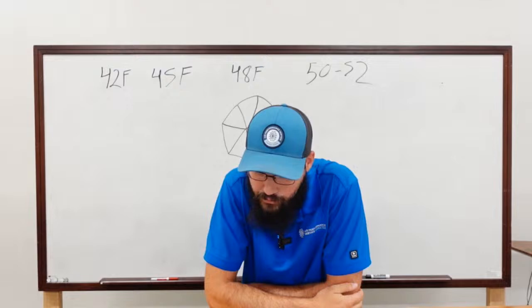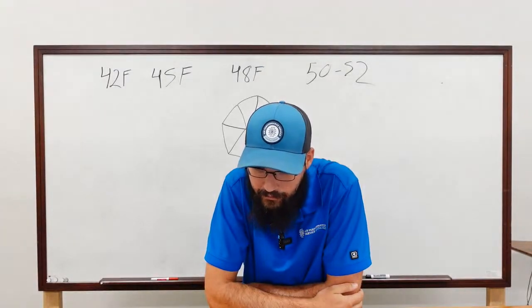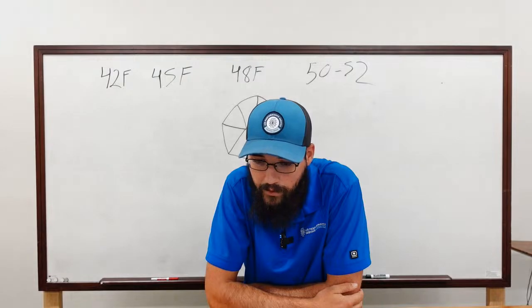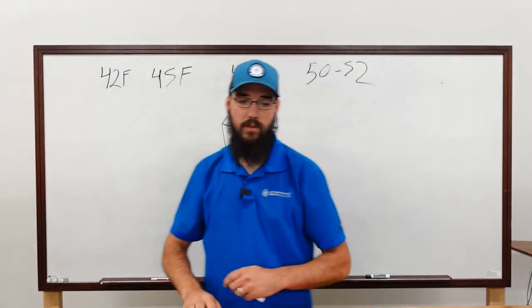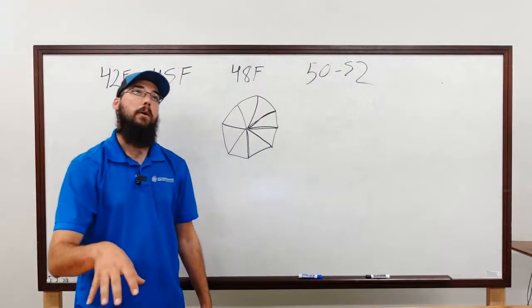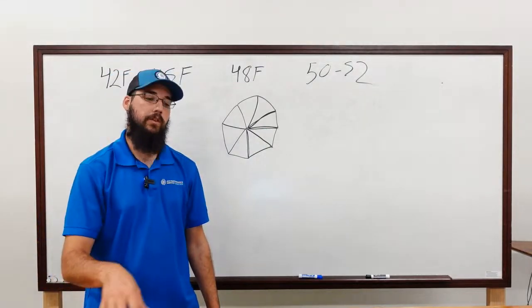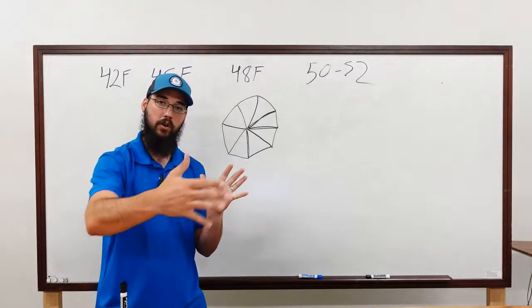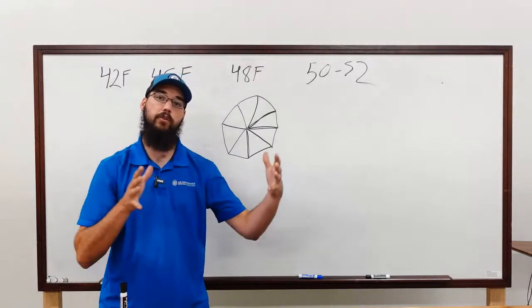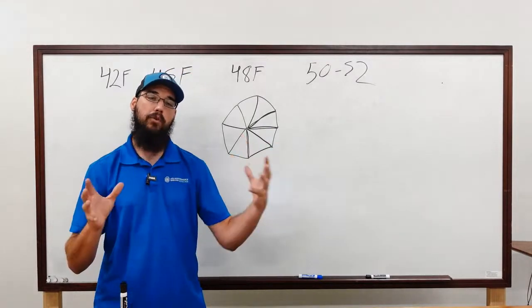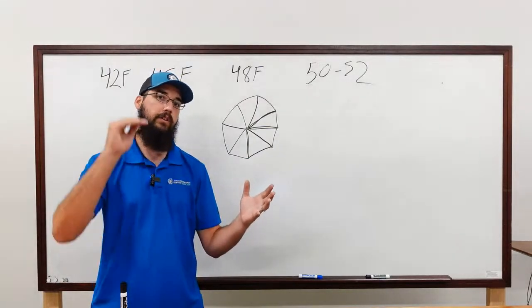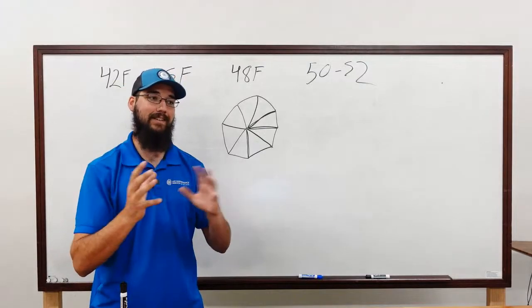See, Sterling, when there's a two-screw, two-circuit chiller, is it better to have the second screw only come on once the first one is running at half the load, or run both? Yes. So, Sterling, that's exactly part of how it works. Whether the chiller itself or the chillers are networked together and running their own independent control sequence, or whether they're doing it through a building automation, in both scenarios that chiller, despite how many circuits it has, is going to fully stage up and fully stage down in this staging sequence.